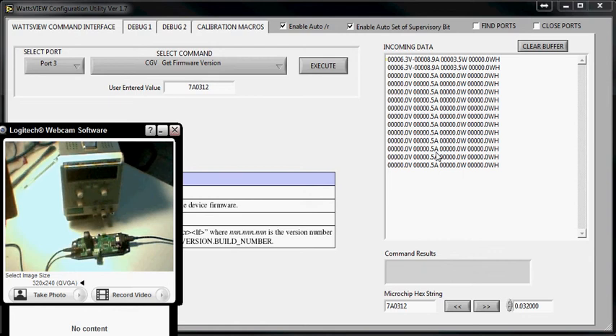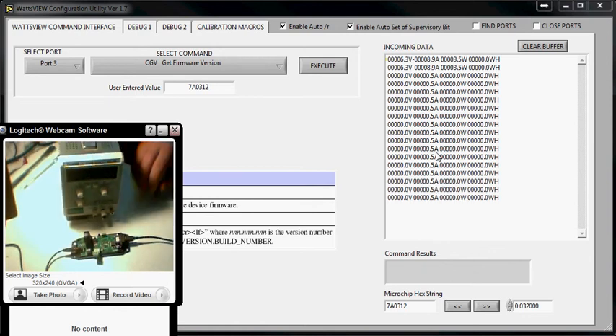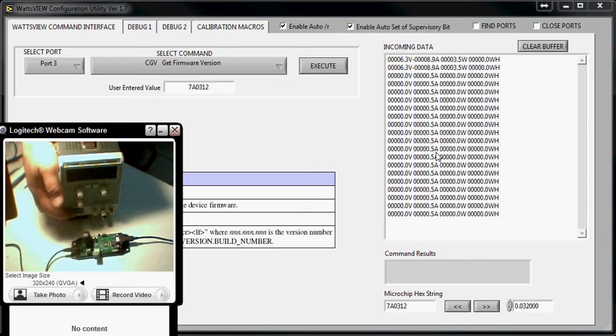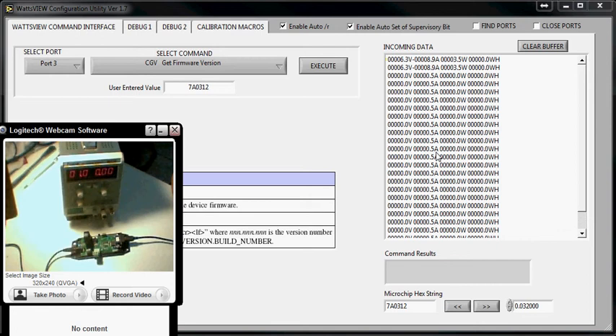The next step is to get a power supply, or something like a 12-volt battery would work. For the current test, you want to put out at least 3 amps. In this case, this sensor can measure over 100 amps of current, so the more current you put through the sensor right here, the more accurate you can do your calibration.